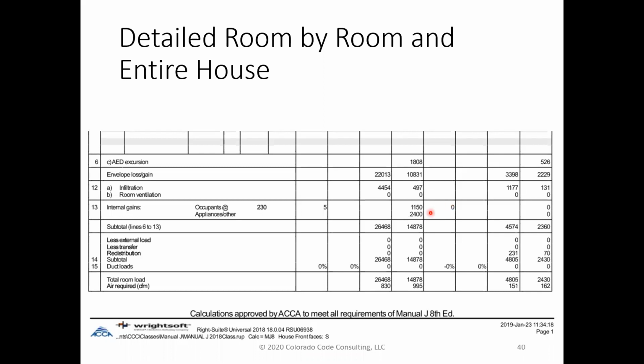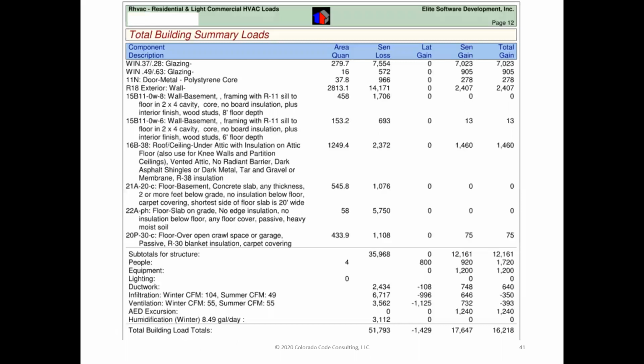My comment was, please show your calculation for that. And he certainly did, and included everything except the additional kitchen sink. It was clearly something that he was trying to make it bigger than it needed to be. Okay, so those are the 2 important pieces: number of people and appliances. They got a TV room, they should include it.